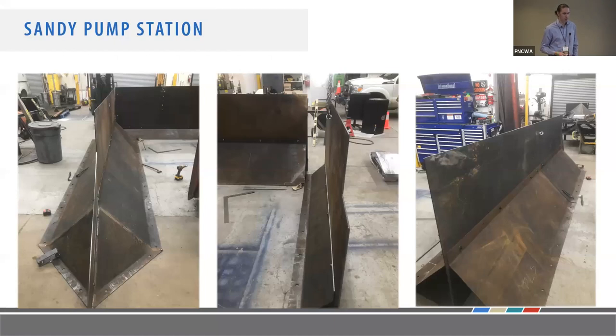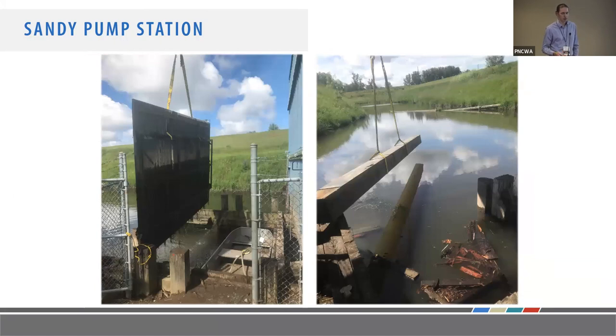The project has been built. The floor cones and baffles were fabricated, the bar screen was removed, decking was taken away, and divers installed all components without dewatering. Divers sent photos of the wet well interior. The CFD analysis across multiple criteria provided significant benefit, justifying the installation of these components and the associated construction costs.